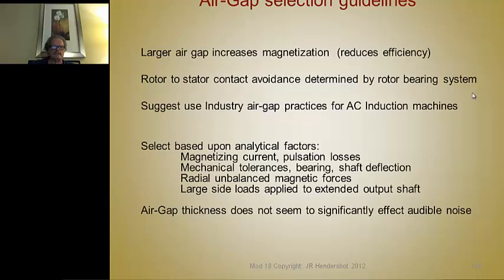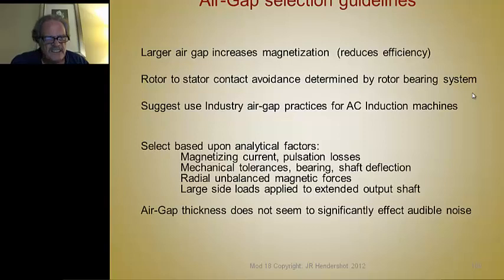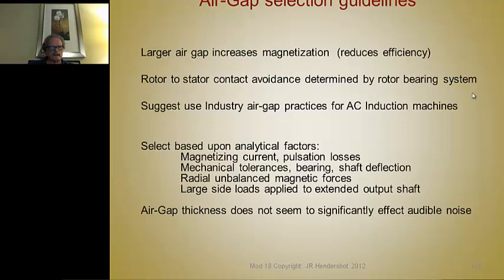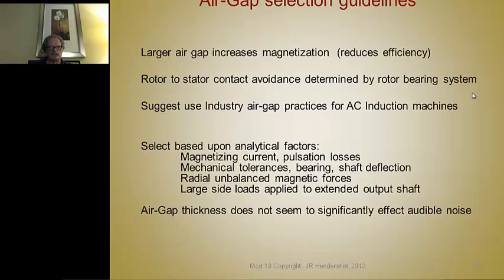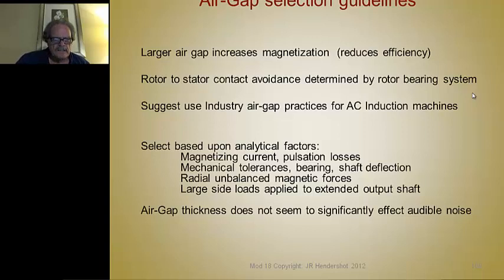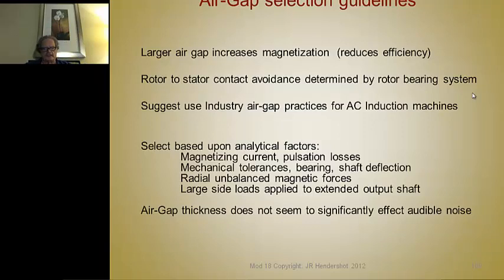The front bearing — the one supporting load, gear loads, belt loads, pulley loads, coupling loads — many times needs to be clamped so the outer race can't skid and gall out the bearing bore, particularly if the end bell is aluminum instead of steel. Standard gap practices are recommended, using accepted practices for all manufacturing tolerances, magnetizing current, rotational losses, side loads, and shaft support. The air gap thickness does not seem to significantly affect audible noise in most cases, but sometimes it does.